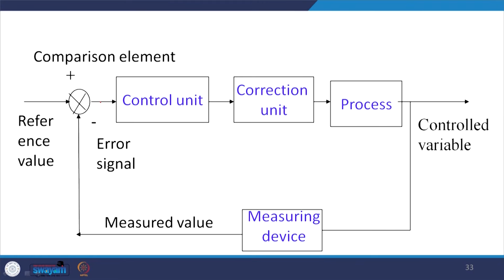A very good example of a closed loop system is the shaft speed control, where there is a motor and we tap the output speed of the motor. With the help of a bevel gear arrangement, the shaft of the bevel gear drives a tacho generator, and the output of the tacho generator is in the form of voltage. We compare that with the DC supply, that is the potentiometer value which sets the reference value, and this difference signal is given to the differential amplifier, which amplifies the difference between the reference and actual value, and then it drives the motor.